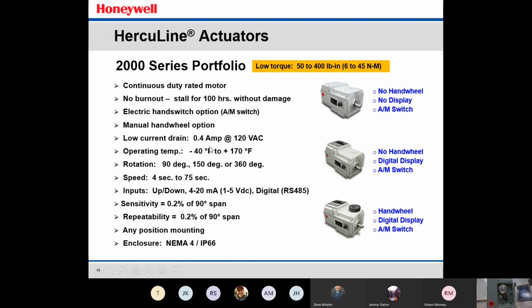It is important to let you know that it has a stall for 100 hours without any damage. So this stall that is in the actuator is rated for 2 times its rated torque and at 100 hours without any damage. So you can see that these actuators are rated very conservative at 400 inch-pounds, but understand that it can actually see twice that up to 100 hours without any damage.